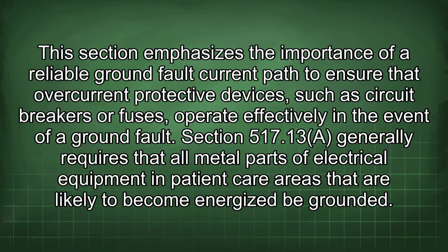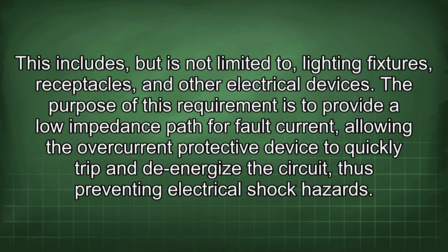Section 517.13 generally requires that all metal parts of electrical equipment in patient care areas that are likely to become energized be grounded. This includes, but is not limited to, lighting fixtures, receptacles, and other electrical devices. The purpose of this requirement is to provide a low-impedance path for fault current, allowing the overcurrent protective device to quickly trip and de-energize the circuit, thus preventing electrical shock hazards.